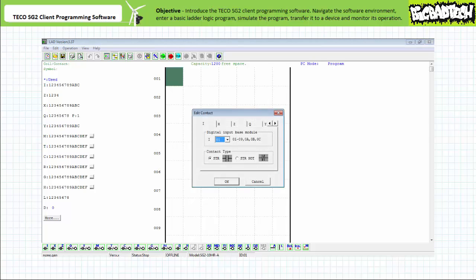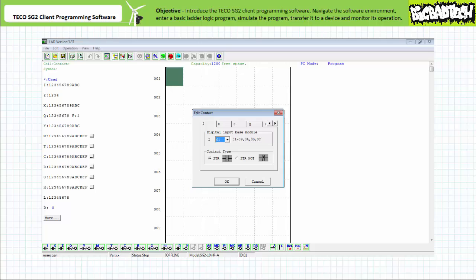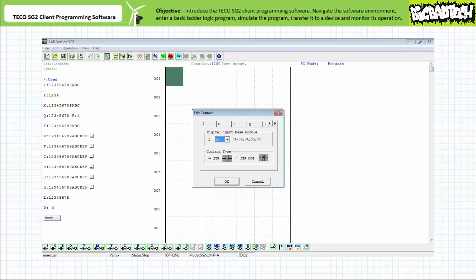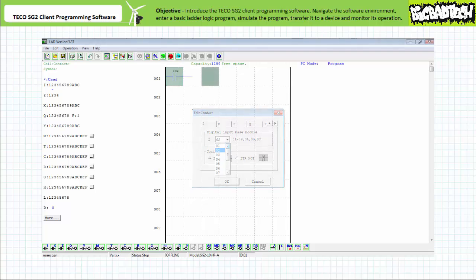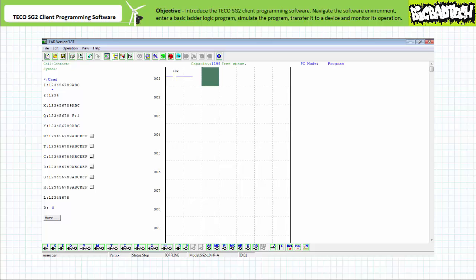To add a contact or coil to the program, press the button for the contact or coil of interest and then click the desired destination on the workspace. Here I've added an I input instruction into rung one column A. A pop-up menu allows a user to select basic properties like operand number and make or break behavior. Additionally, tabs allow a user to toggle between alternate functions like timers, counters, and more. We'll examine these additional functions in later lectures. Note that within the TECO SG2 client programming software environment, contacts are designated using ANSI CSA format. However, an actual device will display this program subtly differently on the small LCD screen using device format, where a make instruction is designated using capital letters and a break instruction is designated using lowercase letters.